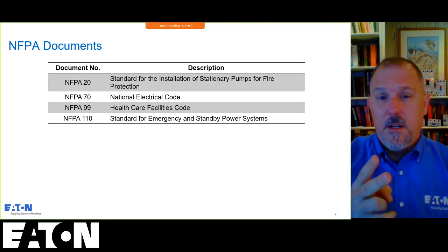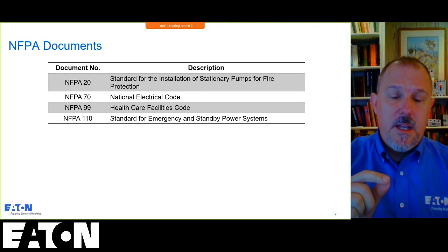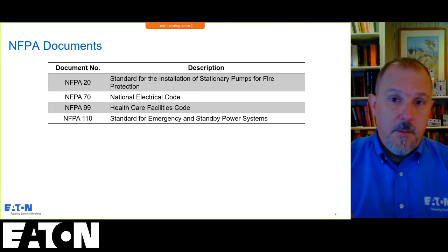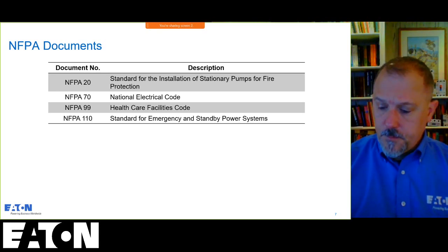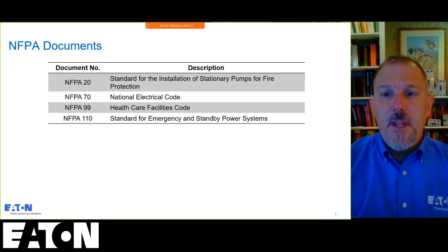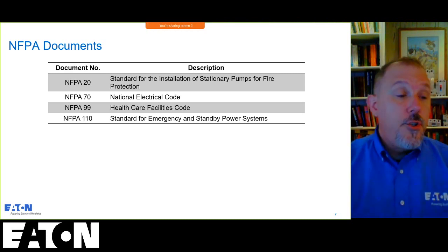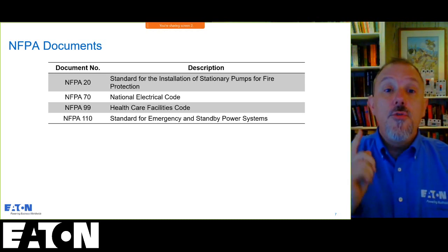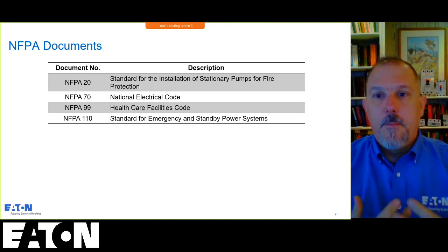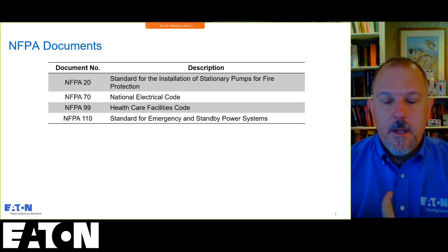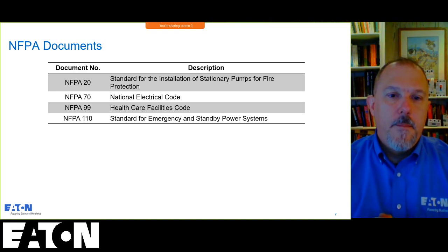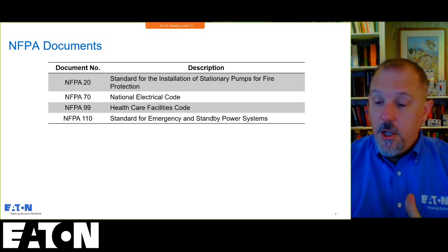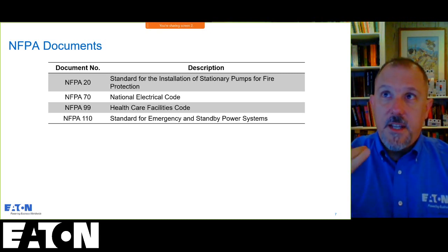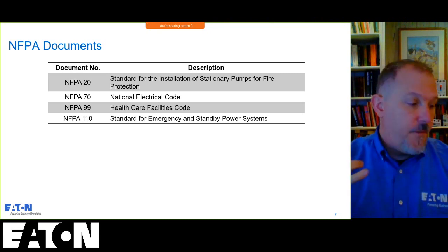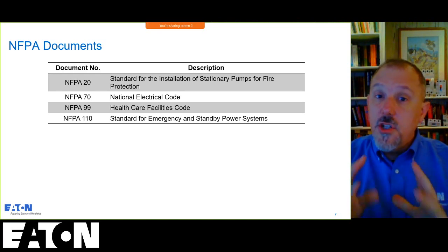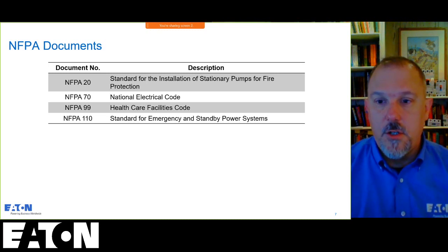Now, another key document, two other key documents I would say, but one in specific would be NFPA 70B for maintenance. I'm on that committee. We are in the process of updating that document, and we're taking NFPA 70B for maintenance from a could, should, you might want to document to a shall document. So we're taking it from a guide to a requirement, a standard. I call it the trilogy. You have NFPA 70, which is the National Electrical Code, 70E, which is electrical safety, and 70B, which is maintenance. Those three work together to help build a very good, safe electrical system.